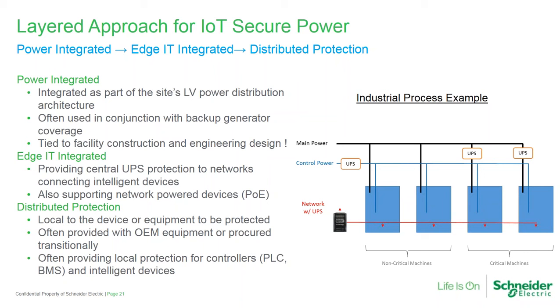The types of UPSs that Schneider and others provide are typically what we call a double conversion UPS, meaning you're relying on the UPS to generate power. The battery backup is backing up the UPS, not the machine itself, so you're constantly not touching utility power directly.